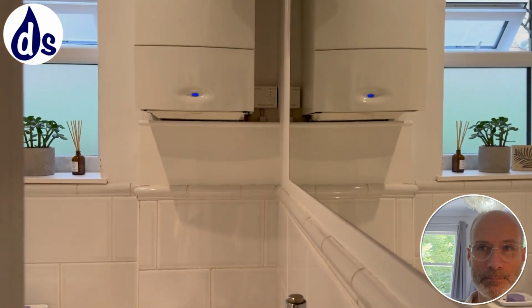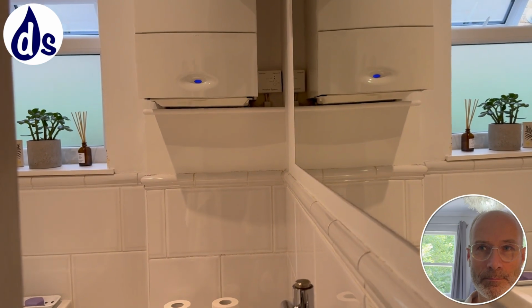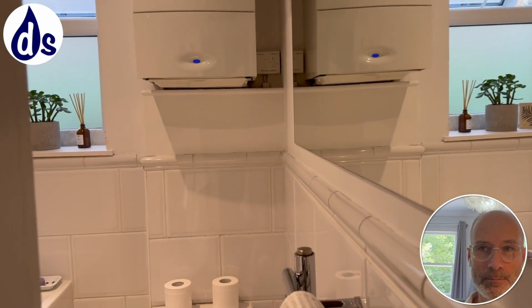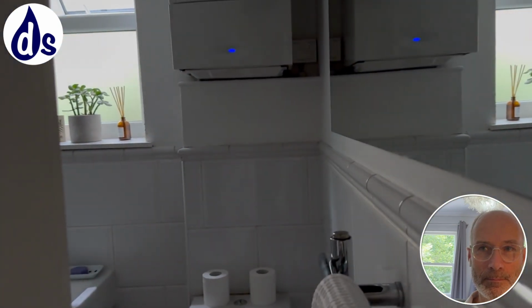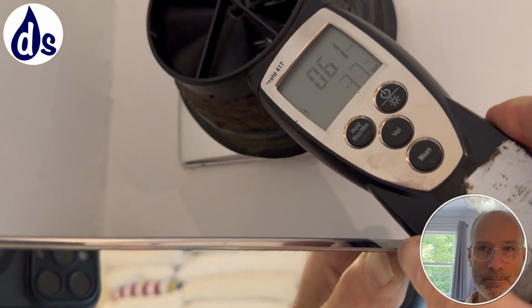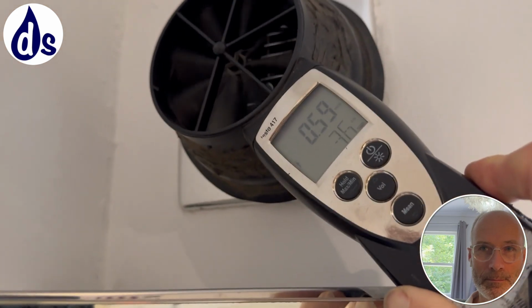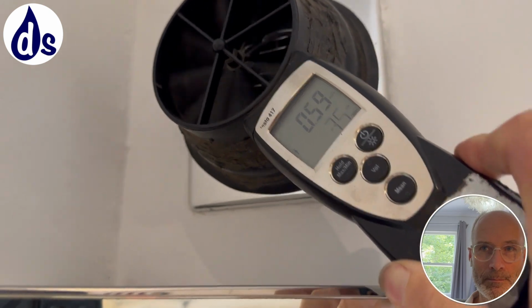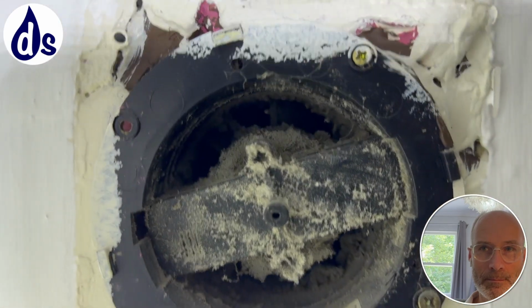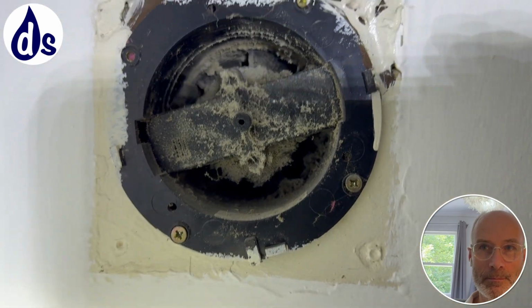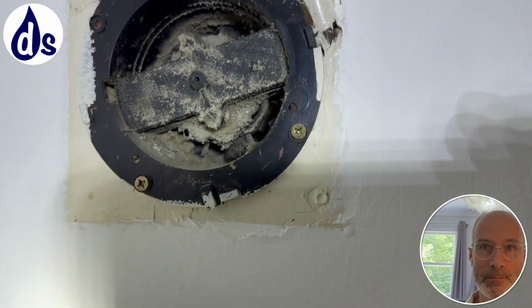And then the bathroom extractor fan turns off immediately when you turn the lights off. But if you have the door closed and the window open, that's effective as well. So we're running at 3.7, should be 15. We might be able to clean this up and improve it. See, it's quite dusty there. I'm going to take it off and inspect it.